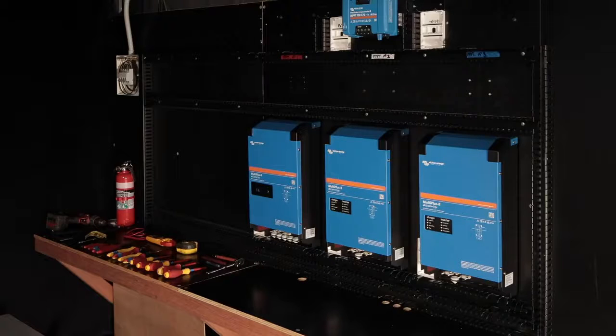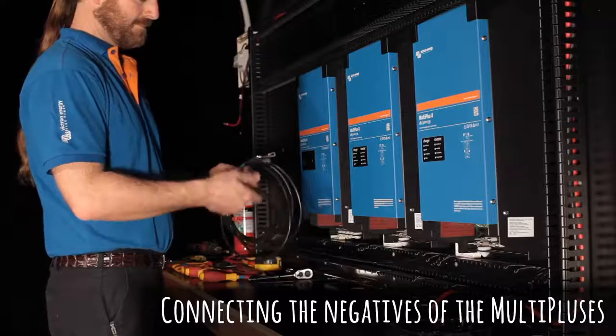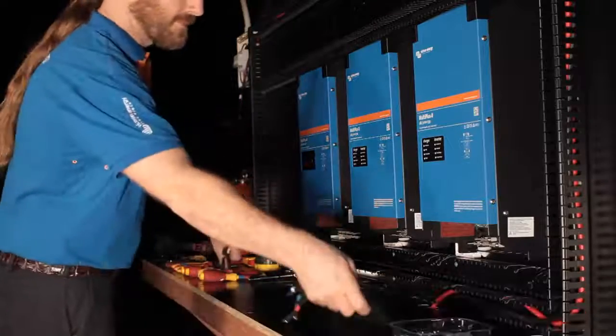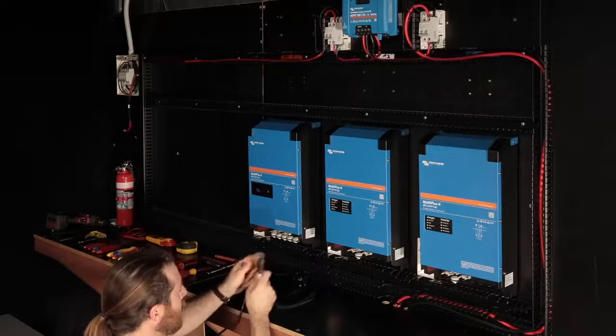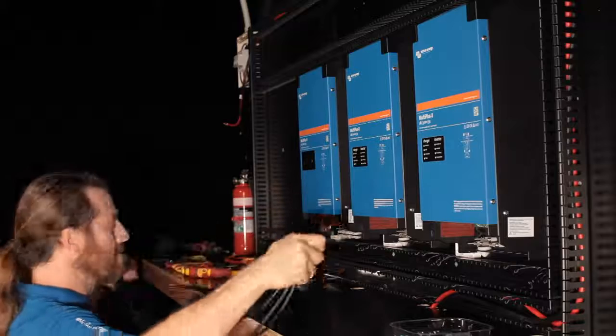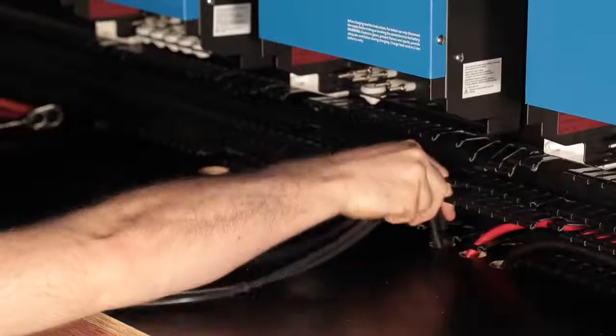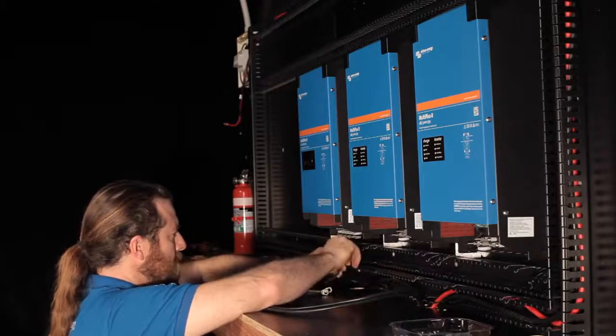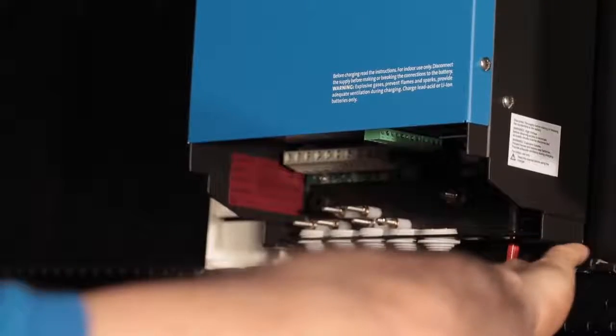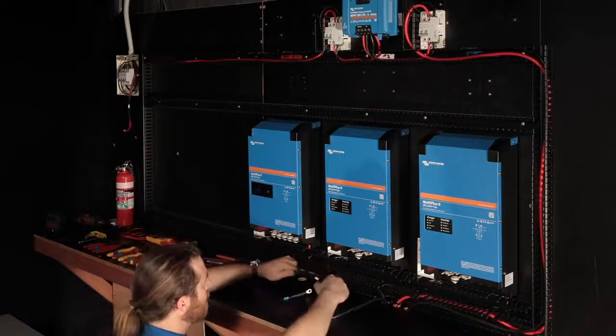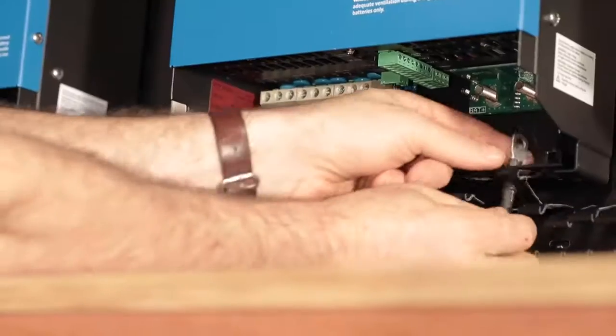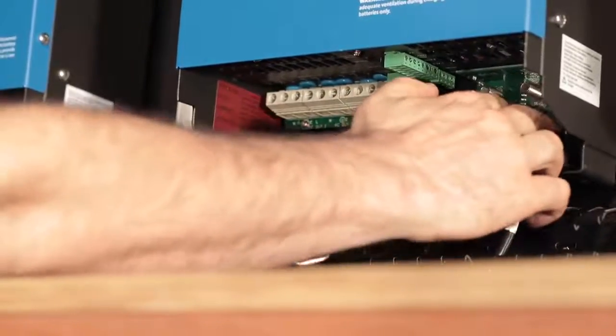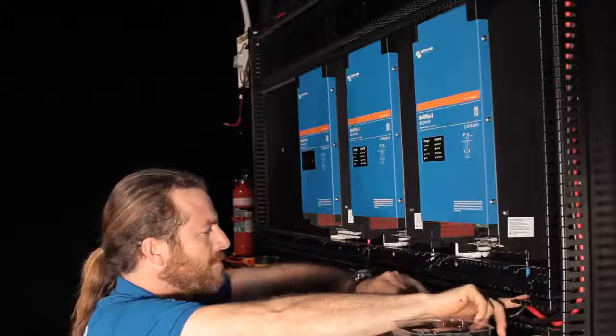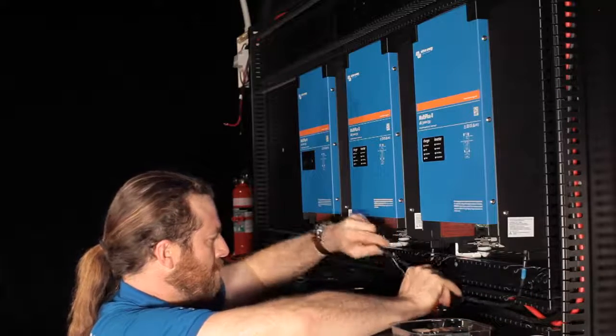We'll now connect the Multiplus 2s with the negative battery cables. If you're connecting a parallel system together, it's very important that these cables are equal length, so cut them all together to the farthest unit. If it's going to be a 3-phase system, this is less important. It's important that the negative cables are a continuous uninterrupted length between the 3 Multiplus units and the DC distribution. They can't be cut or switched in any way. You should also definitely connect these battery negative cables to the bus before we connect communications cables.